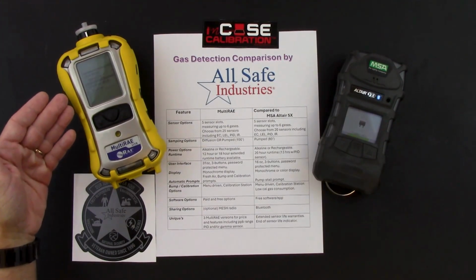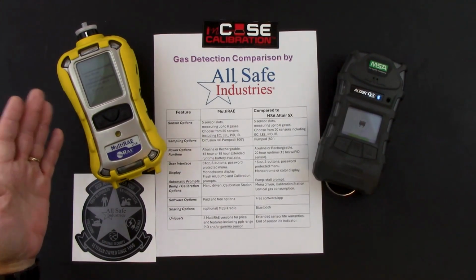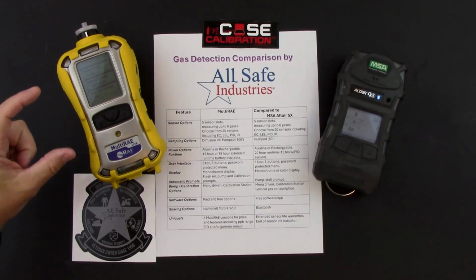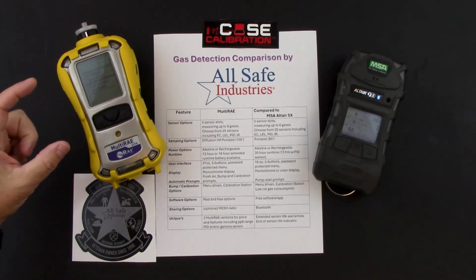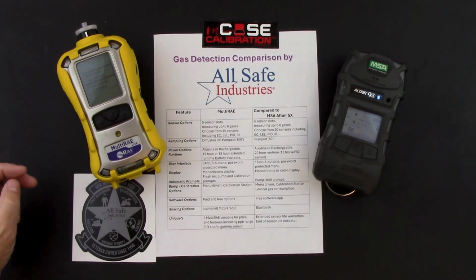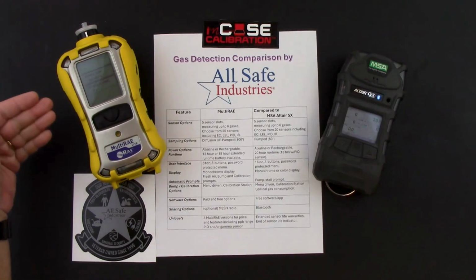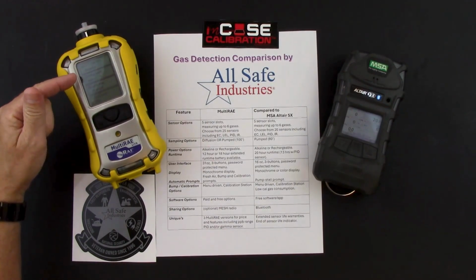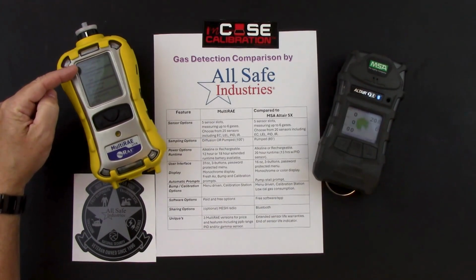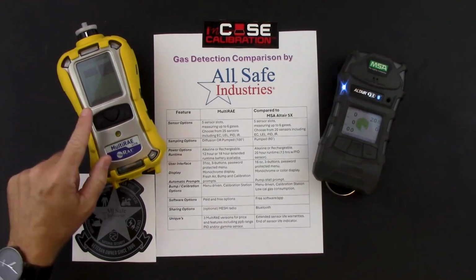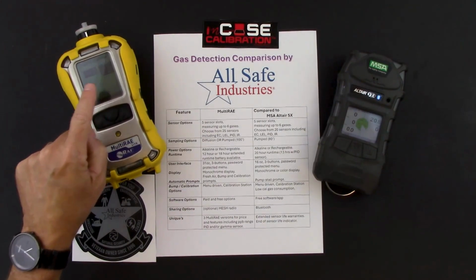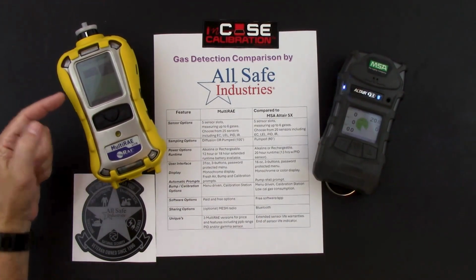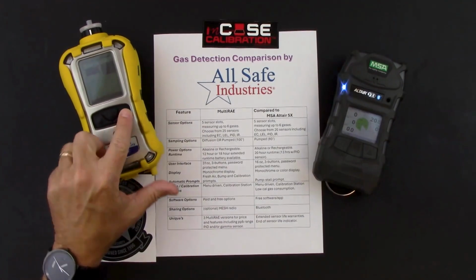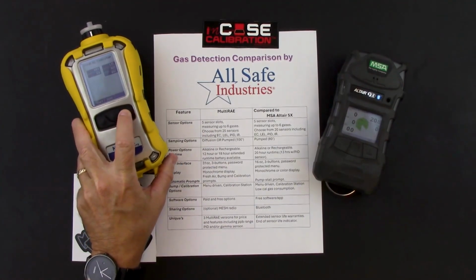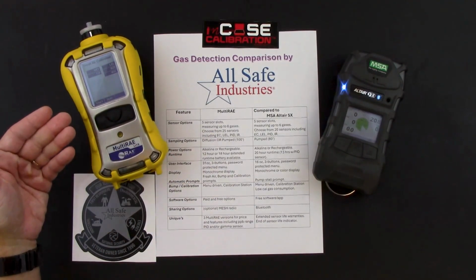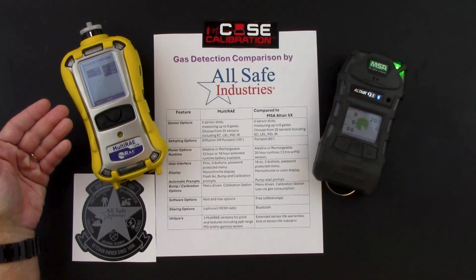My MultiRAE had started giving me information, same kind of details. We'll run through each sensor that's installed, what my different alarm set points are. Now I'm getting towards the end of the warm-up here where I'm seeing my data logged information, some of those automatic prompts, and then I finally get to the first automatic prompt on a MultiRAE, which is asking me for a fresh air calibration. Now I don't have to do a fresh air calibration. I could certainly use the meter without doing this step.